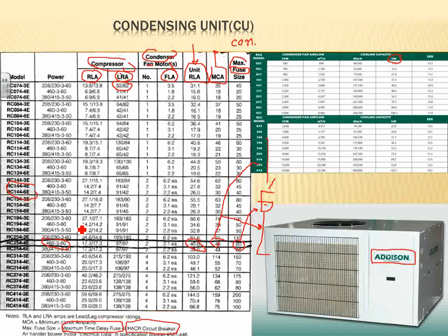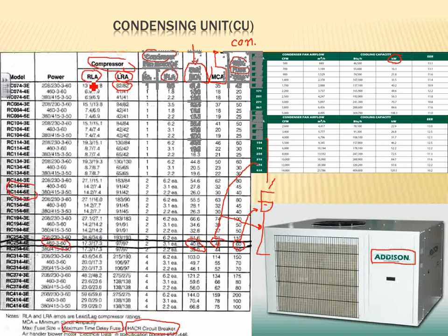Okay, so which one are we taking there for the 115%? Because you've got the unit, and then you've got the compressor. You put all in there, right? Yes. Technically, when you're going to do that, they have the unit rated load amps. In this case, we have a compressor rated load amps and a condenser fan. You're going to take these two amps and add them up together. So that will get you the full load current of the fan as well as the compressor.